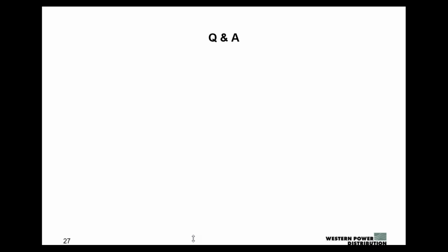So we've got a question on here from Tim about significant constraints in parts of WPD which could benefit from flexible power, and whether we're going to be looking to increase those zones. So the answer to that is yes. What we've endeavoured to do this time around is assess all of the load-related reinforcement that we've got on the network out to the end of 2023. So any schemes that we've got identified for reinforcement have been opened up to the market, and we've got the forecasting information, and we're seeking flexibility in those zones. As I say, 334 megawatts worth of flexibility.